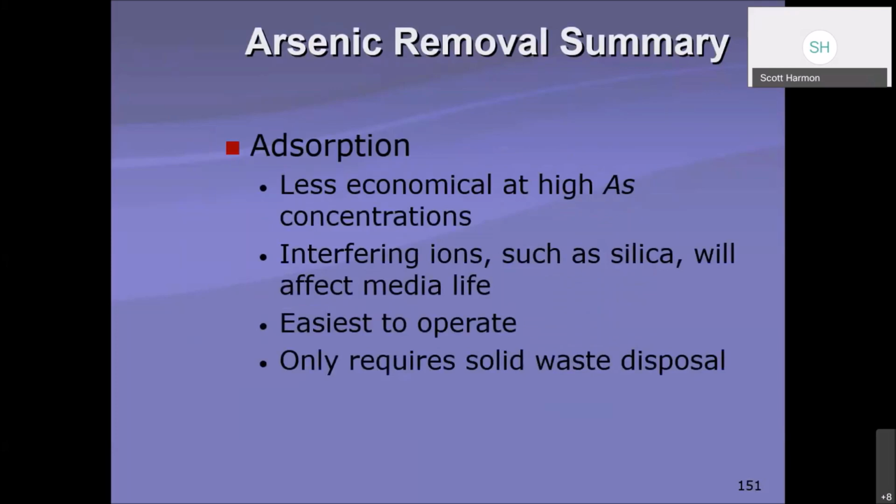So adsorption is less economical at high arsenic concentrations. There are lots of interfering ions that can affect it, such as silica, which will affect the media life because it will bind with that adsorptive media. It's easiest to operate in that you're just adding some filters essentially to the process, or you may be retrofitting existing filters that you have into the process. It only requires solid waste disposal because you're talking about sludge, probably iron and manganese associated with the arsenic as well.